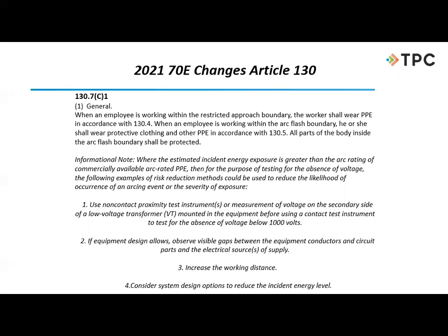They're telling us now that we could reduce the likelihood of something occurring, like an arc flash, by using first some type of non-contact tester. That would be no problem. We could go ahead and do that before we use the contact tester. So we would only use the non-contact tester to give us a little bit of indication that there might not be any voltage present there. But then we would have to put our contact tester on it. And sometimes, if the equipment allows it, we could observe the gaps inside, so that if there were infrared windows there that we could look through, that would also be another method we could use to help us confirm that the contacts did open up.